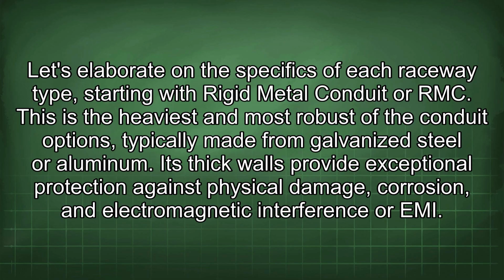Let's elaborate on the specifics of each raceway type, starting with rigid metal conduit or RMC. This is the heaviest and most robust of the conduit options, typically made from galvanized steel or aluminum. Its thick walls provide exceptional protection against physical damage, corrosion, and electromagnetic interference or EMI.